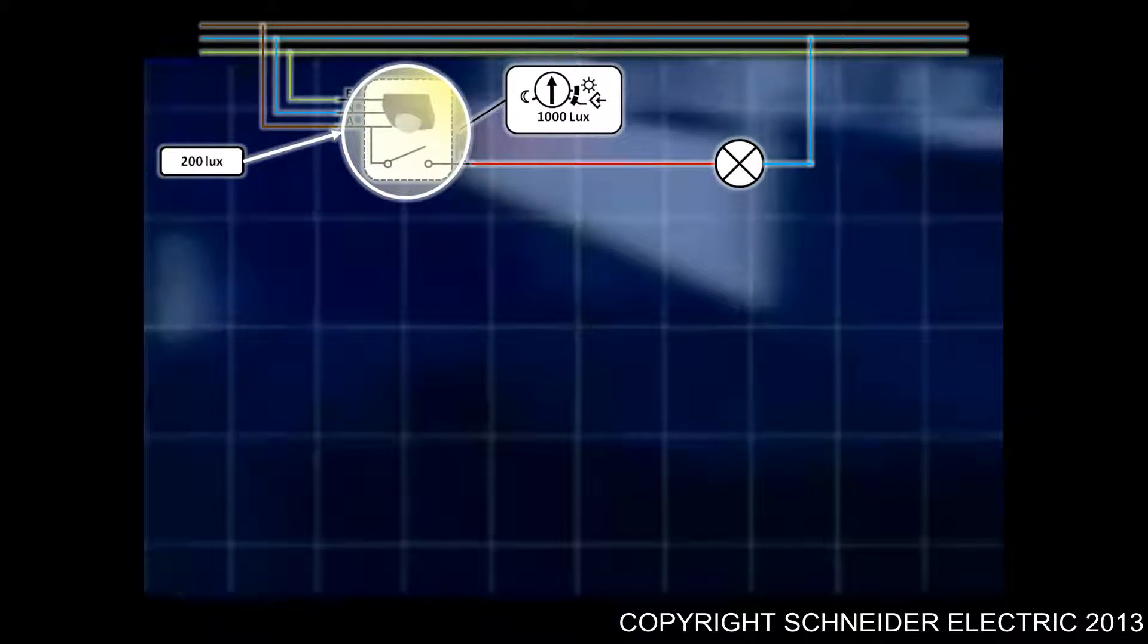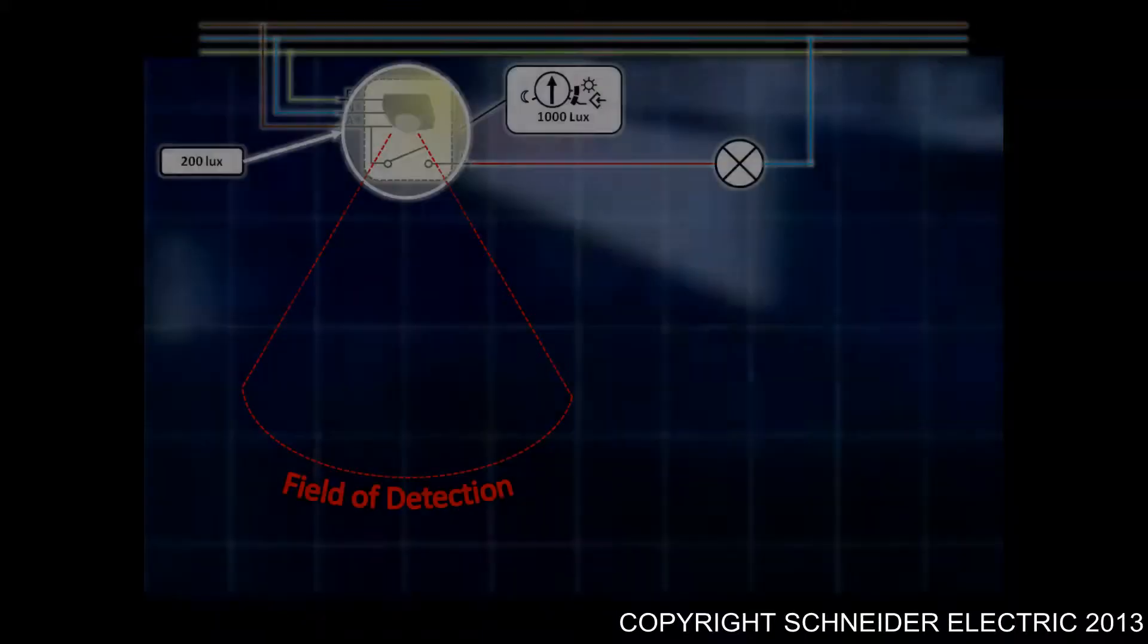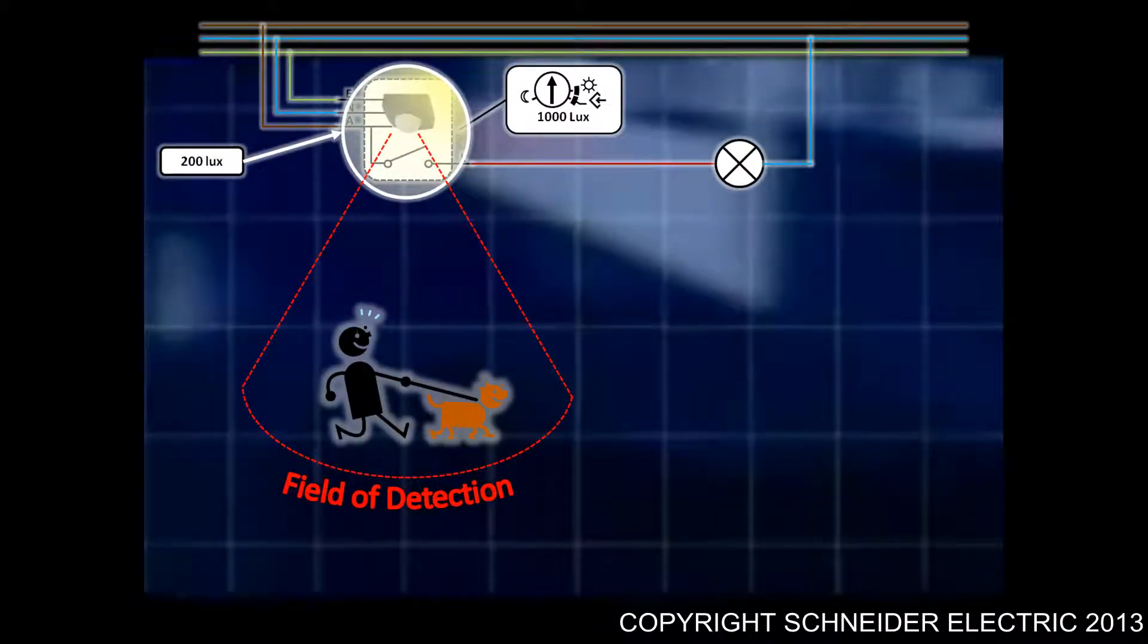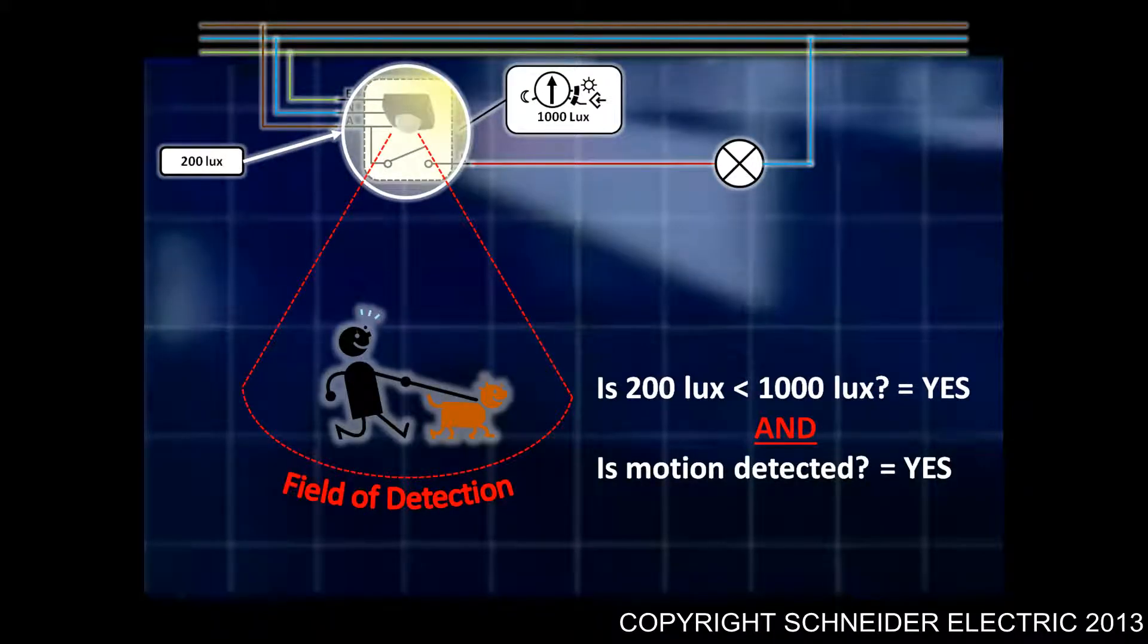What's popped up on this slide is an ambient light level of 200 lux. This is the light of the room or environment in which the sensor is installed. If movement is detected within the field of detection, the sensor basically asks two questions: Is the ambient light, in this case 200 lux, less than 1000 lux, which is that predetermined light level setting? In this case it is.